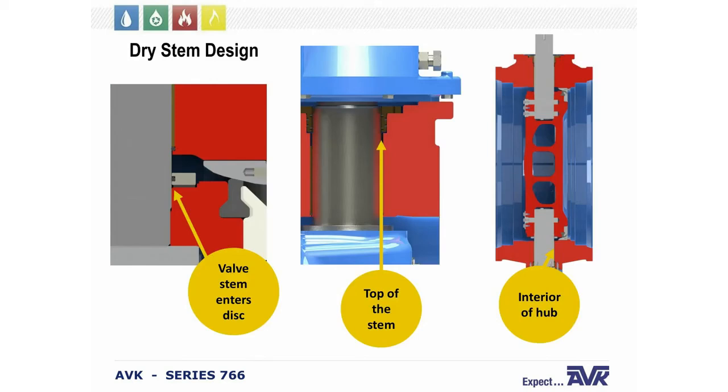The AVK Series 766 is designed to prevent water from entering the stem area of the disc and the valve body. There is an O-ring where the stem enters the disc to prevent water ingress. We have an O-ring cartridge at the top and bottom of the valve body to seal against water entry. The interior of the hub — the valve body — is sealed with O-rings as well, preventing corrosion inside the disc and protecting the pins that operate the valve.